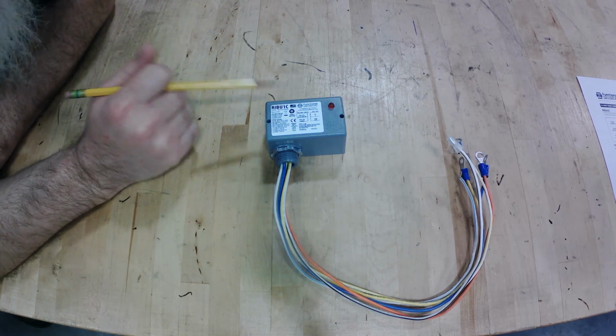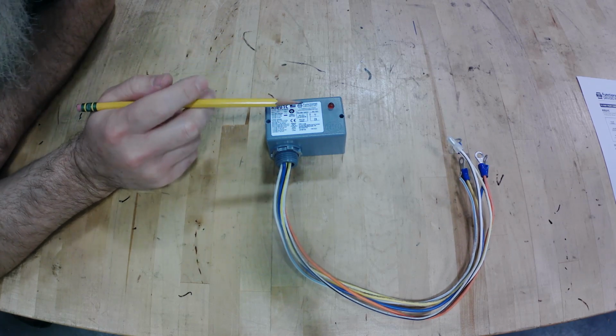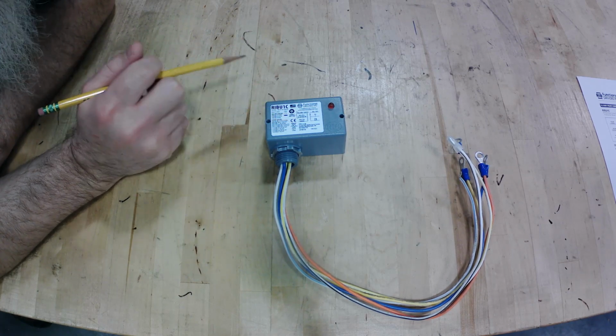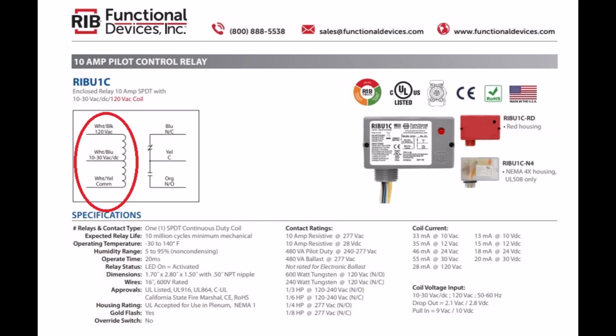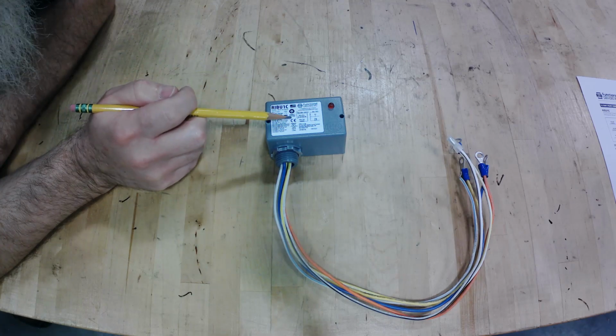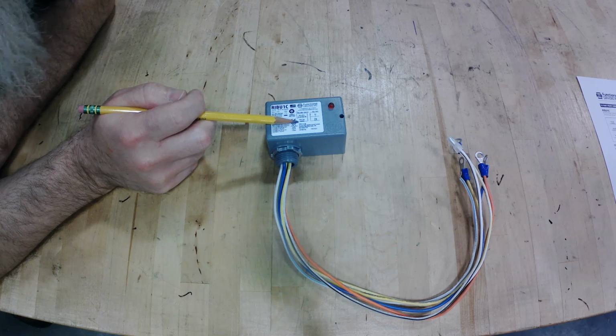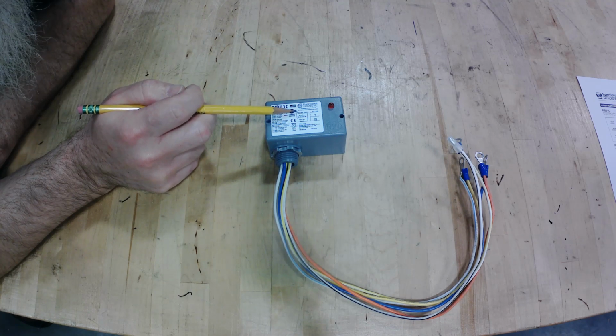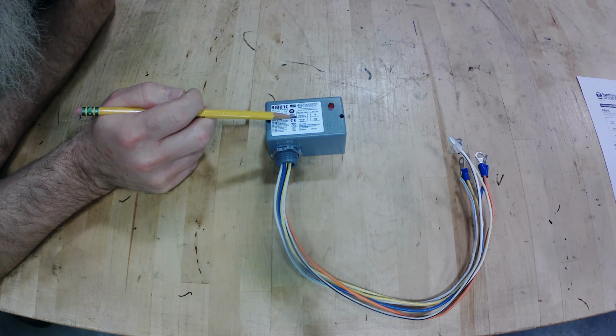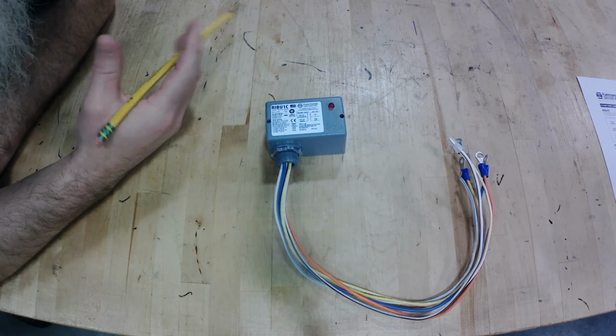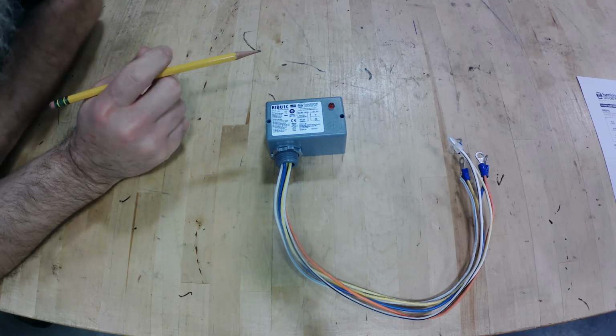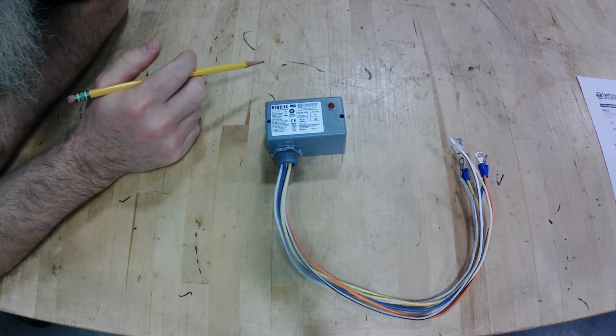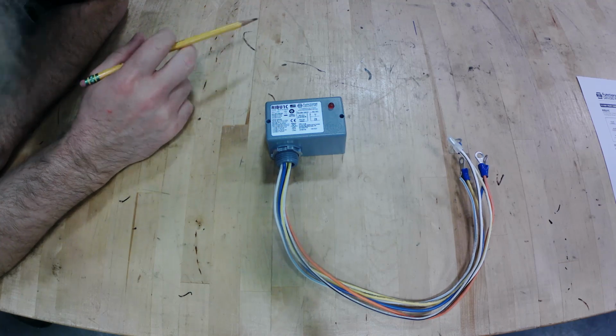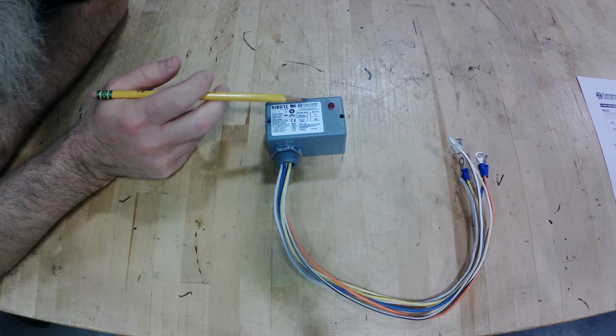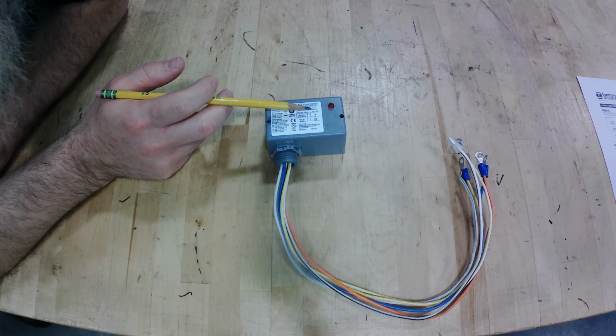On top of it, I'll throw up the spec sheet real quick, but you've got your coil voltages listed. What we can do here, we have a common connection and 120 volts AC to the coil, or you can use 10 to 30 volts AC or DC, which falls in line with our residential style 24 volt control system. So I'm going to use it in our Aries air handler that we've done before. Coil voltage on this side, and if you look on the other side, there's going to be your switches.